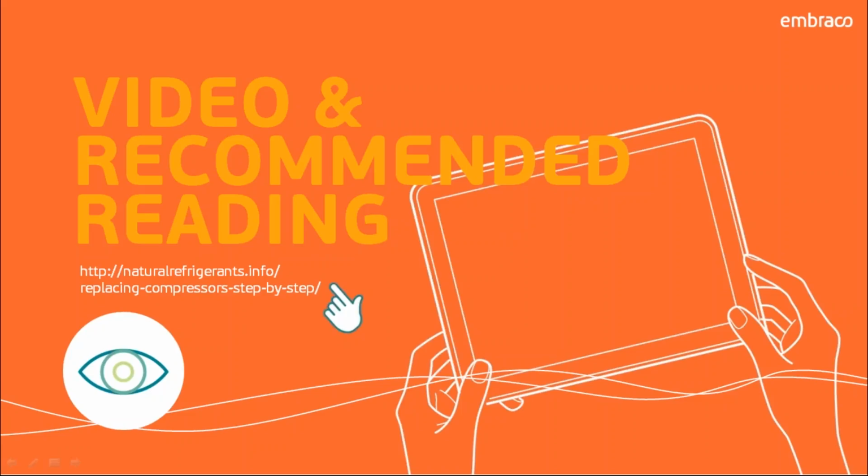Okay. Do regular leak detectors pick up R290? No, I would say no. I don't think they currently do. That's some research that technicians should do, because I'm not even sure that a regular combustible gas detector, like for natural gas, picks up hydrocarbons. I would do some research on that and see if a regular combustible leak detector will pick that up. If not, we'll have to get hydrocarbon specific. But yeah, contact the Ritchies and all the other manufacturers, Inficon and all of them. I would do some research and talk to some people about that, because a lot of this stuff is still so new. There's still a lot to learn for everybody. So that's definitely something to do some research on.